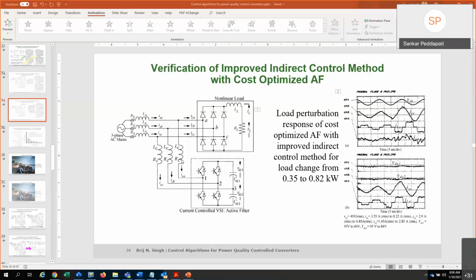Sure. So for example, most drives have a front end rectification, right? Imagine there is one inverter here, then electric machine control. You can connect your electric drive, particularly an industrial drive, not electric vehicle, to the supply coming in. Since the front end converter is a diode rectifier, and the inverter controls the machine, that's called a diode rectifier based system.